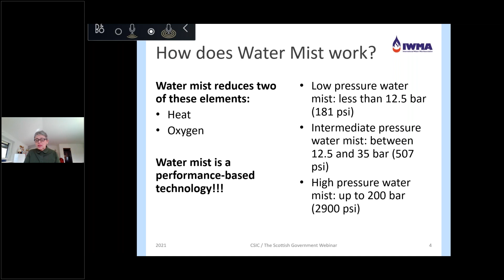Here you can see that NFPA, the National Fire Protection Association, a US American association, and the European Committee for Standardization have a slightly different opinion when it comes to the number of droplets that should be less than 1 millimeter or 1000 microns in size. However, what is more important than whether 90 or 99% of the droplets are less than 1 millimeter is the fact that water mist is defined by droplet size, and that the droplets a water mist system produces interact with the fire so as to reduce the heat and the oxygen, as I already mentioned. The droplet size is a result of the pressure of the system, but also of the type of nozzle. And the smaller the droplets, the quicker they evaporate.